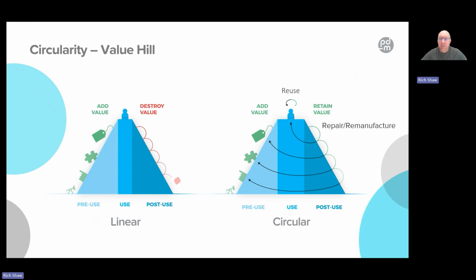If a product gets damaged or needs some repair, that can be facilitated and then the product returned back to that original user. So a good example of this might be a surgical device, a stainless steel instrument that may get blunt over time. It can go off to a specialist repair service, they can sharpen it, they can make repairs to it, they can regrind it, polish it, re-sterilize it, and then get it back to that user. When things get a little bit beyond that, there might be a more significant refurbishment required. That may then be sold as a refurbished product, not even necessarily to the original user.